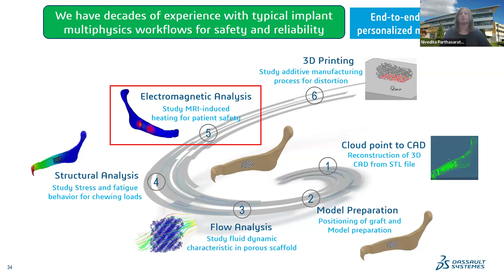So when it comes to med devices, the main keyword is safety. And this isn't just a nice to have, it's a regulatory requirement with very strict limits on how it can be used with humans. And this isn't exclusive to implants. So, with the picture of the MRI machine that you see here, being able to certify the safety using specific absorption rates and other KPIs is an integral part of the development process. But of course, it can become more complicated with an implant. We cannot launch the product unless we actually have the compliance ready. And we're not dealing with just a patient setting, but we need to take into account additional electronics too. And often this falls on the medical equipment manufacturer, not on the MRI device manufacturer.